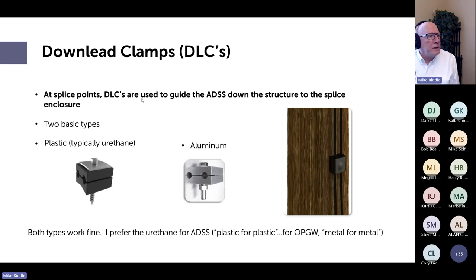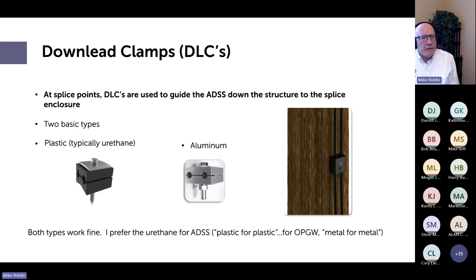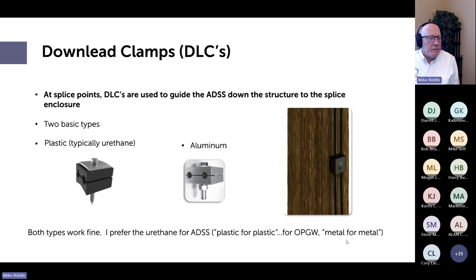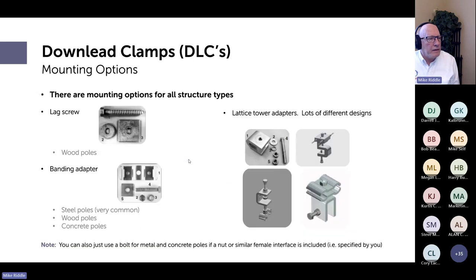Next: down lead clamps. At splice points, you need to guide the cable down the structure to the splice enclosure. There are two basic types: plastic (typically urethane) and aluminum. Both are fine. I tend to recommend urethane for ADSS and metal for OPGW — plastic to plastic, metal to metal. For mounting: lag screw, banding adapter, or lattice tower adapters are all available.